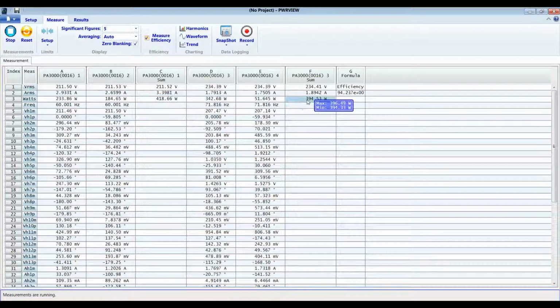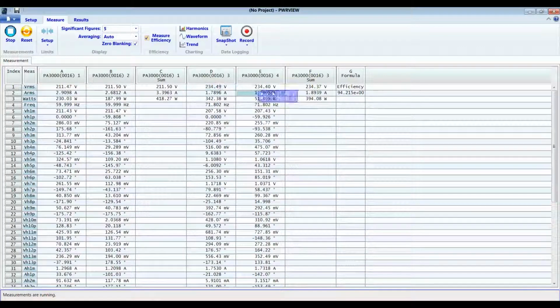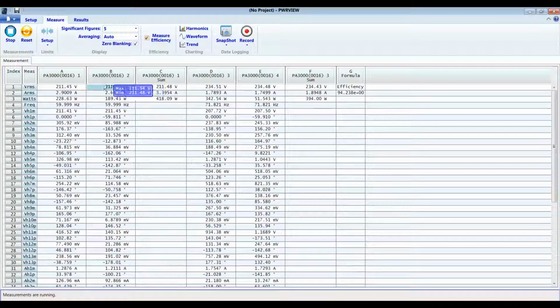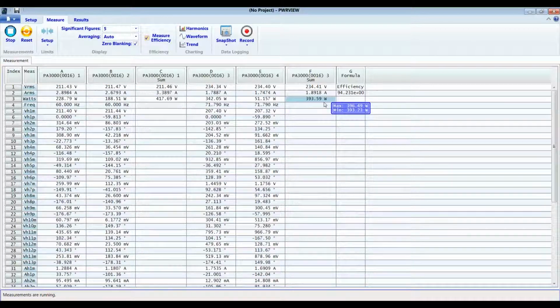Keep in mind that the connections are in a 3-phase 3-wire system, which means the individual voltages on each channel don't have much significance. Okay, those are just phase to phase voltages, like phase A to phase C, phase B to phase C, right, and not phase to neutral voltages. Now we can check the efficiency on PWM drive right here. It's that simple.